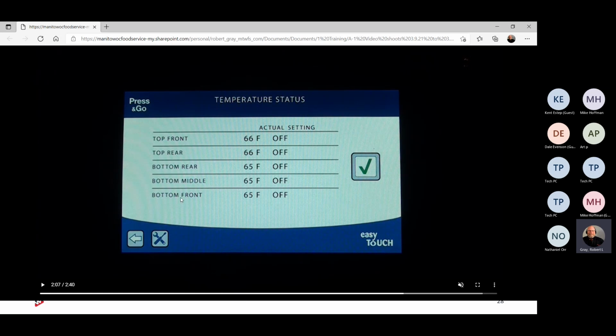Again, there are 5 heating zones per lane. There is one user interface, or UI, per lane. That UI operates the lane that it's located in. One thing I'm going to say: when you're in temperature status and you want to exit out, don't use your green check mark or your diagnostic button here. If you use your green check mark, it's going to take you back to the home screen. If you use the diagnostic button, it's going to take you into the diagnostic tab of the programming. If you use the back arrow, it takes you back to wherever you were before you pushed that thermometer button.